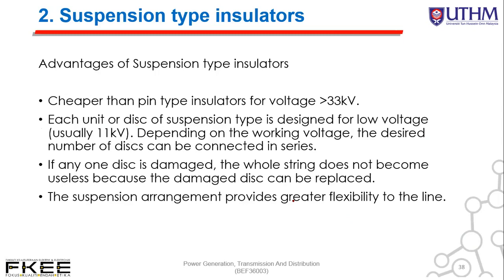Advantages of the suspension type insulator: first, it is cheaper than pin type for voltages above 33 kV. Second, each unit or disc is designed for 11 kV, so the desired number of discs can be connected in series depending on the working voltage. Third, if only one disc is damaged, the whole string does not become useless because the damaged disc can be replaced. The suspension arrangement also provides greater flexibility to the line.